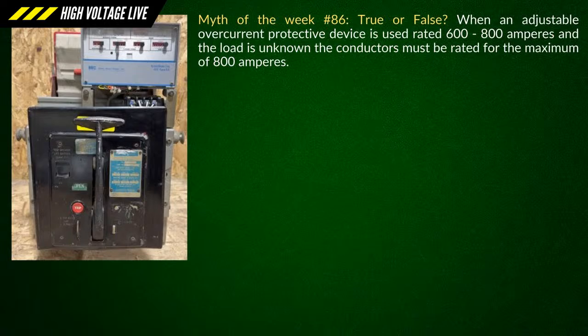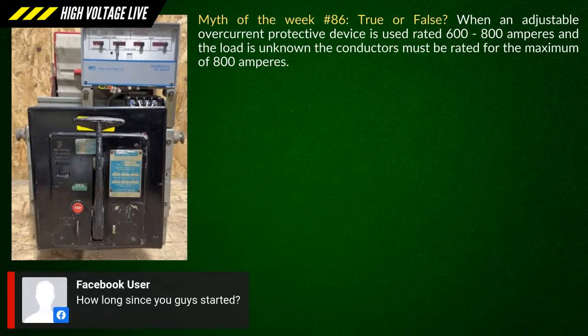The reason I put the unknown load is, this could be some kind of industrial AC unit, and they could say max breaker 800, minimum conductor size 600. Well, guess what? You're totally fine with having a conductor sized for 600 with the equipment ground sized for 600. The overcurrent device can be set to whatever the max breaker is, and you're good to go. But in this case, we don't know that.